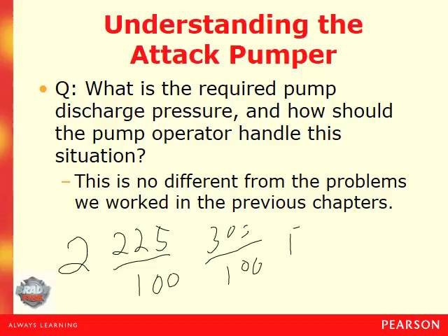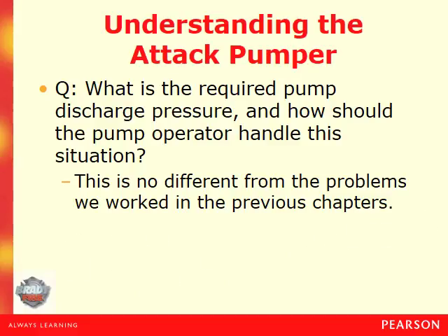So our friction loss equals 2 times 2.25 squared times 3. When we multiply all that out, we get about 30.375, or we'll call it 30.38 for round numbers. So our friction loss for the first one is 30.38.